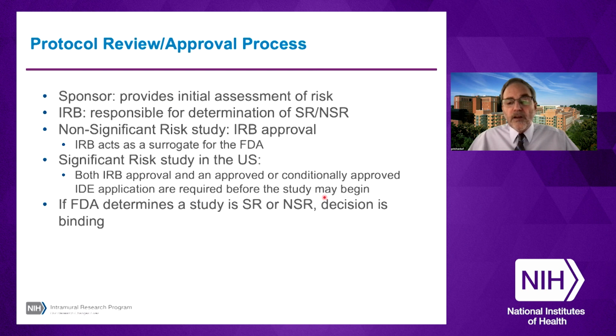Now, in this setting, the FDA delegates its authority to the IRBs to make this determination, and the IRB acts as their surrogate. If it's a non-significant risk study that the IRB approves, then it's subject to what are called the abbreviated IDE requirements, and those are all available on the FDA website. On the other hand, if the IRB determines that this is a significant risk study, then it will require both IRB approval and an approved or conditionally approved IDE application before the study can begin.